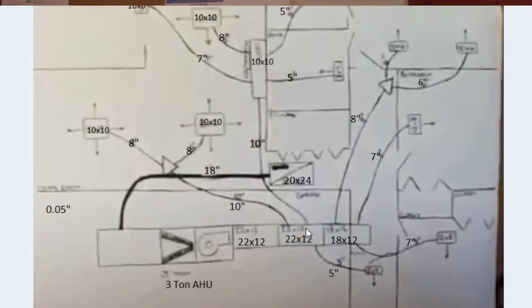We've got a 10-inch flex that's kind of snaked through the attic, it looks like, feeding a 10 by 10 box. Then off of that 10 by 10 box, we have a 7-inch flex feeding, I'm just going to assume, a sidewall register. Okay? Now, when we are looking at that, a 10-inch flex at 4%, the most we are going to get through this 10-inch flex is somewhere between 175 and 300 CFM. Because remember, we have to account for this 10-inch flex, this 10-inch flex, this 8-inch, this 7-inch, this 7-inch, and this 5-inch. The guy that was installing or designing this said that this 5-inch here was free. That was free CFM, okay?